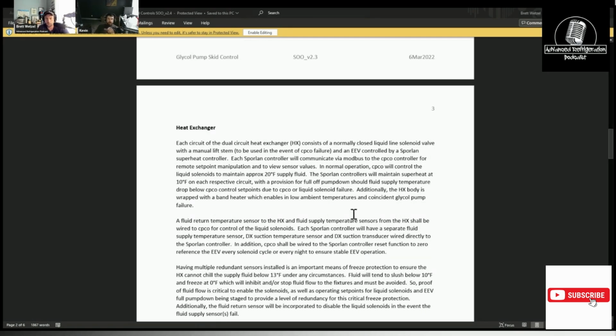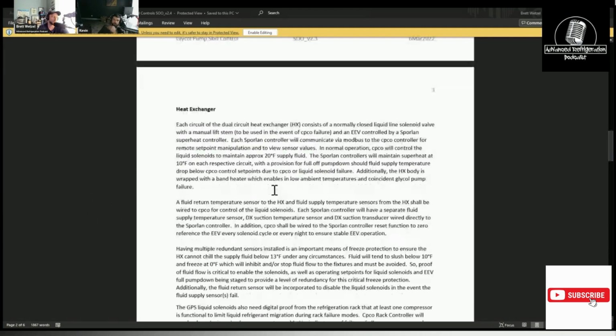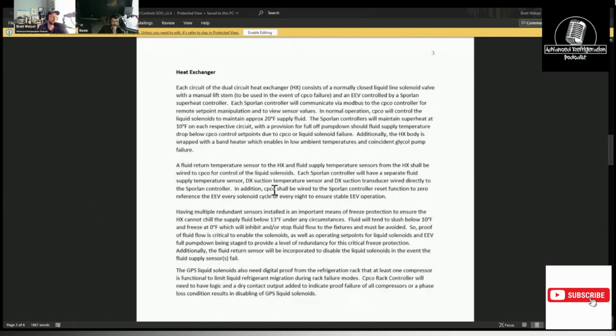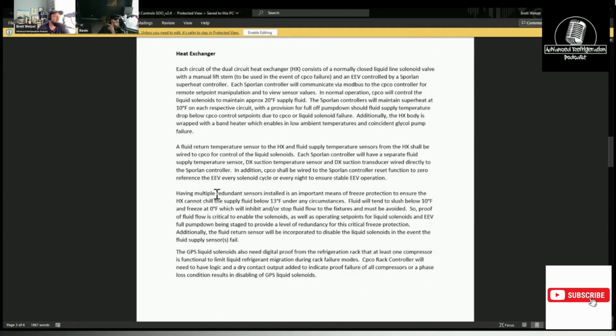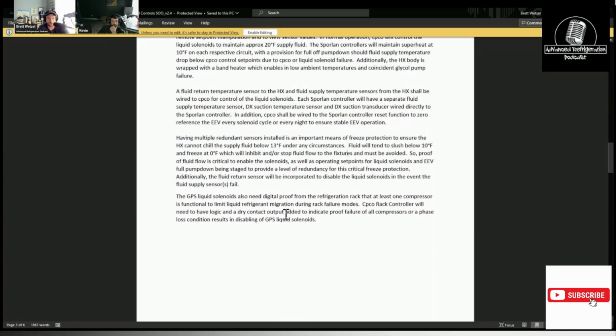The only enable sequence was if the rack was below a 30 SST and there was a call for a pump to run, then it was enabled. Okay, so having multiple redundant sensors, freeze protection. Yeah. If the flow gets down to 13 degrees, and it wasn't getting down to 13 degrees, that's usually what it is, where it actually shuts it off. It has a freeze protection, so it should disable. That should be in the logic of the Carel controller.